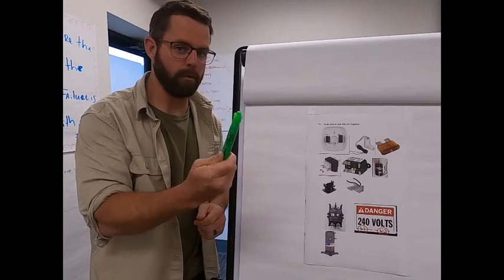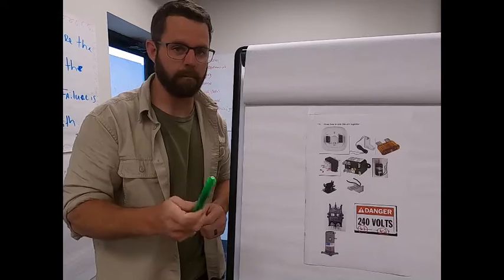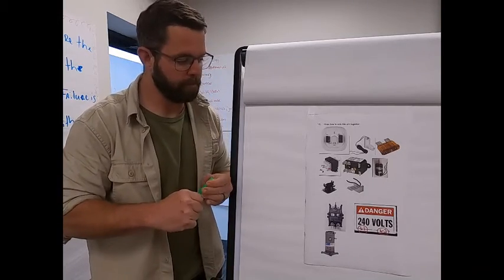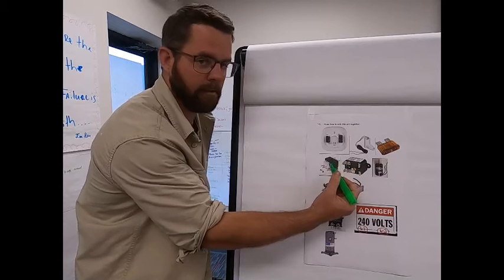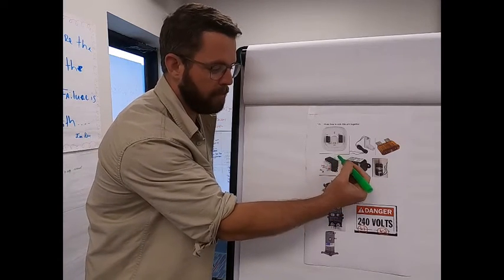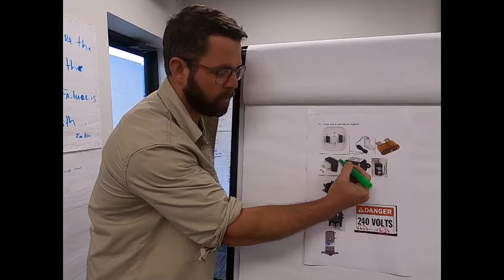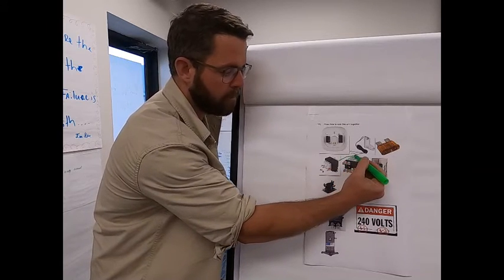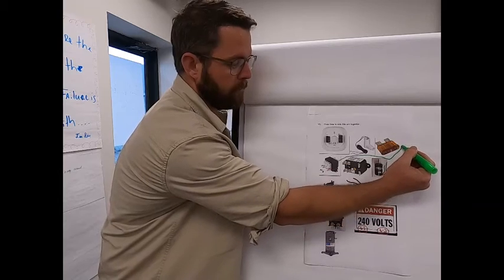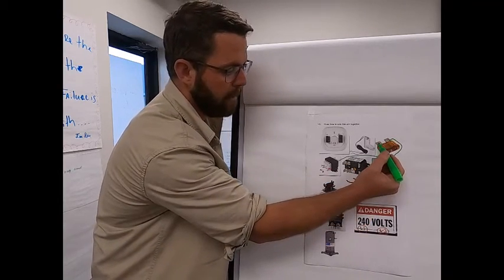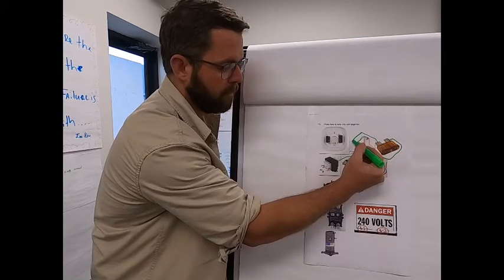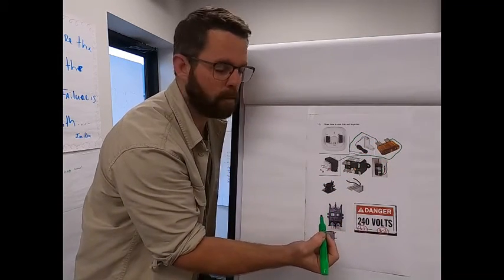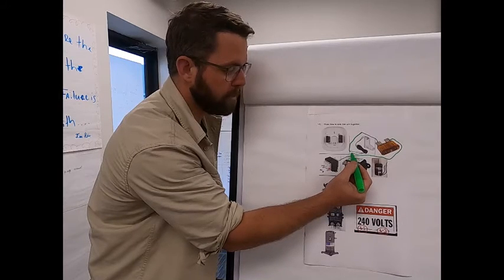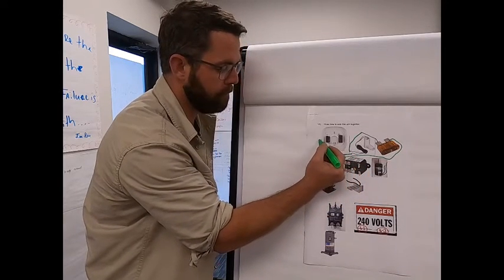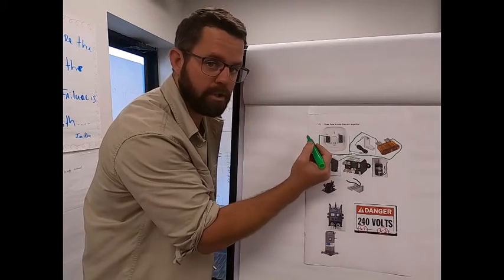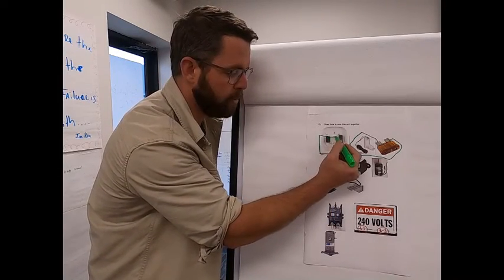I'm going to be drawing low voltage in green and high voltage in black. So our low voltage will be starting at the back of our step-down transformer. We're going to have our wire for 24 volts come first from the transformer to the fuse. Then from the fuse to our safety float switch. After the safety float switch, it is going to come to our R. In this case, we have an RC and an RH, so it's going to go to both.